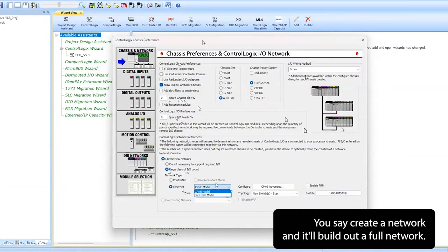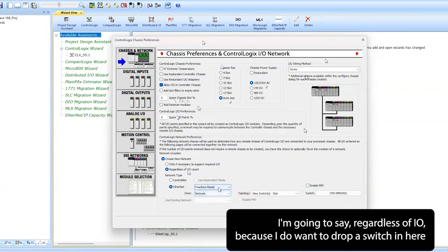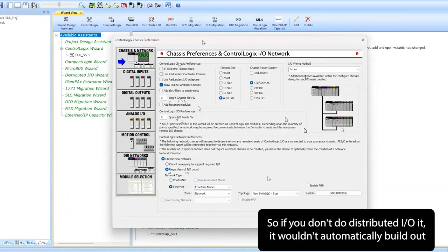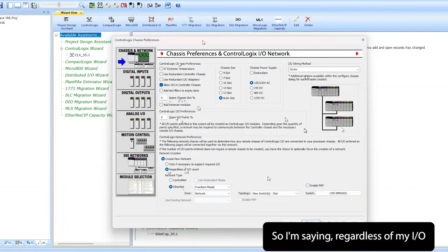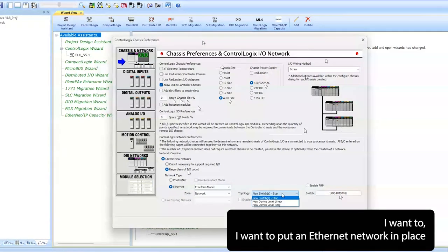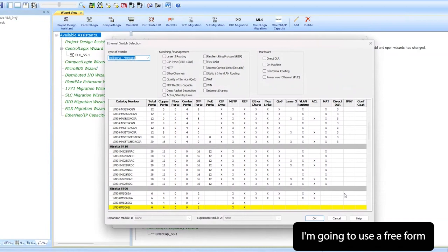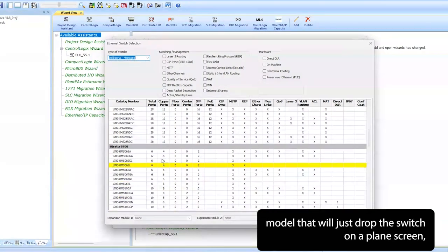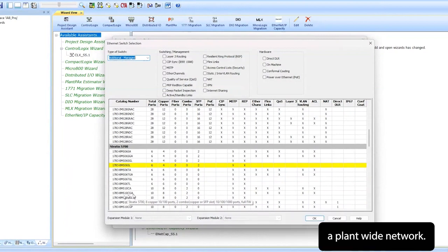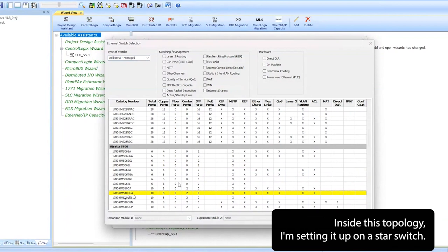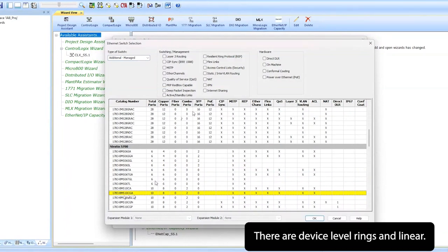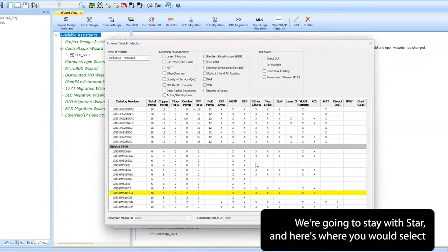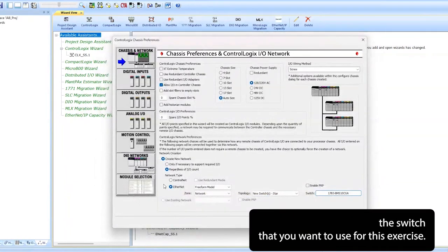Come down, you'd say create a network and it'll build out a full network. I'm going to say regardless of I/O because I do want to drop a switch in here for this design. We're not going to do distributed I/O, so if you don't do distributed I/O it wouldn't automatically build out a network. So I'm saying regardless of my I/O, I want to put an Ethernet network in place. You can play around with these models. For this exercise I'm going to use a freeform model that'll just drop the switch on a plain screen, but know that you could build out a company-wide versus a plant-wide network inside this topology. I'm setting it up on a star switch. There are device-level rings and linears, we're going to stay with star.